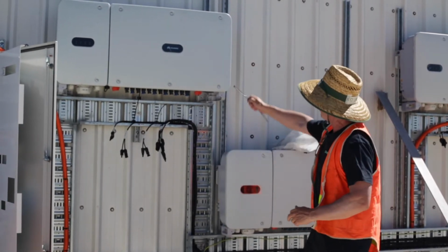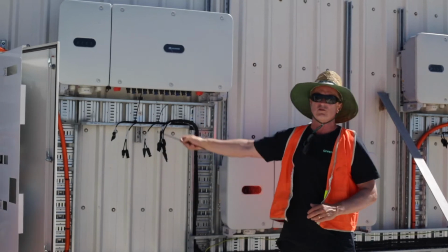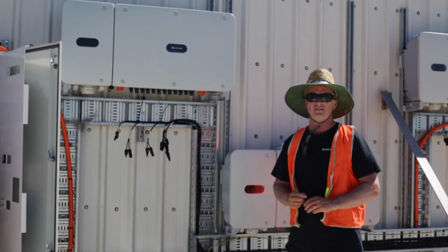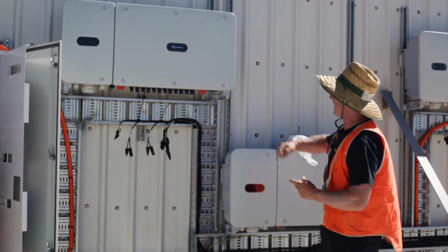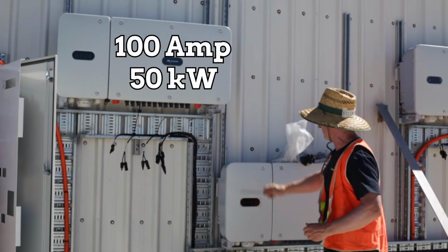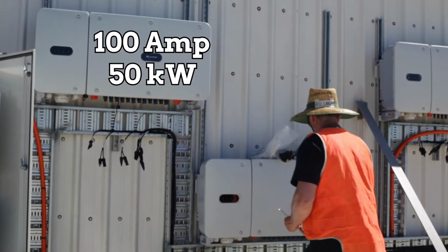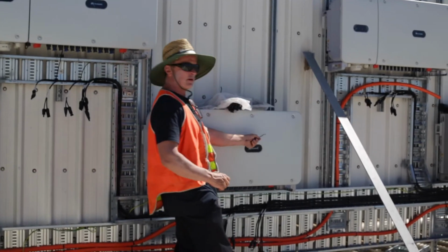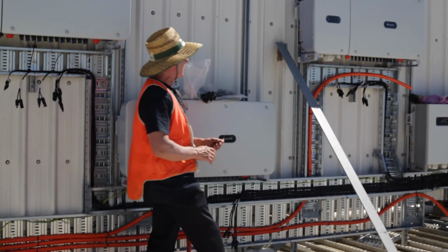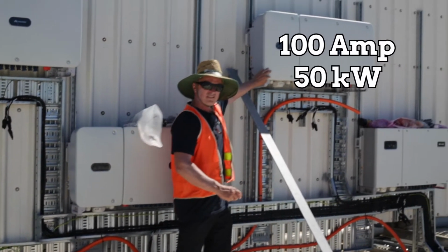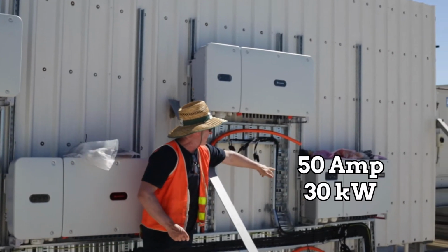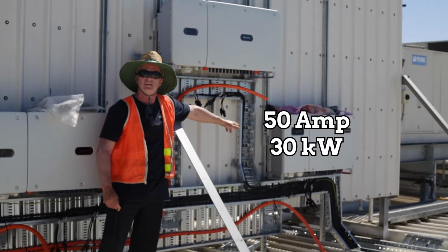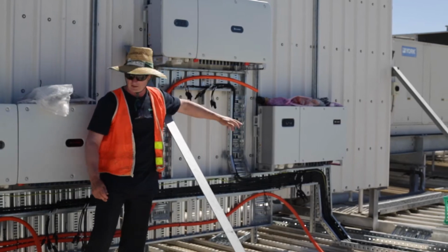In this case, we've gone straight from the inverters straight into those molded case circuit breakers. 100 amps each, 100 for this, 50 kilowatt. 100 for this is a 50 kilowatt as well. 100 for this, 50 kilowatt, and that's a 30 kilowatt, and we're using a 50 amp molded case circuit breaker.